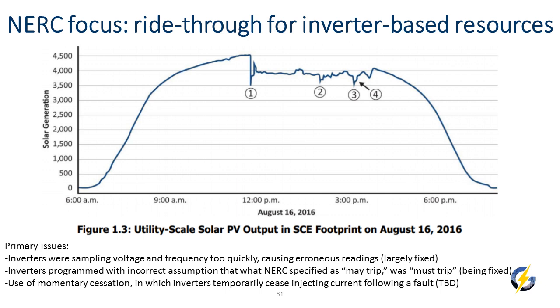As you can see in this event, this is the solar output. There were several very obvious drops over the course of that day as transmission lines tripped. This was due to a wildfire, a very large fire in the southern part of the state that caused several transmission lines to go out of service suddenly. That caused a voltage disturbance that then took offline a good number of these inverters, and you can see them dropping out there. Coming out of this event, there have been a few other events in California with similar behavior, and NERC got very concerned about this.